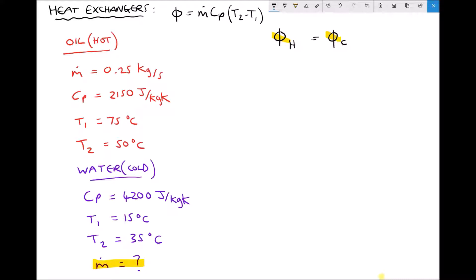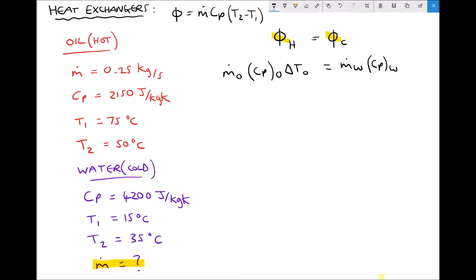Returning to our formula and expanding: on the left hand side we have the mass flow rate of the hot fluid — the oil — times the specific heat capacity of the oil, times the change in temperature for the oil. On the right hand side we have the mass flow rate of the cold fluid — the water — which is what we're trying to find, times the specific heat capacity of the water, times the change in temperature of the water. We know the mass flow rate of the oil is 0.25 kg/s, its specific heat capacity is 2150, and the temperature changes from 75°C down to 50°C, giving a ΔT of 25°C.